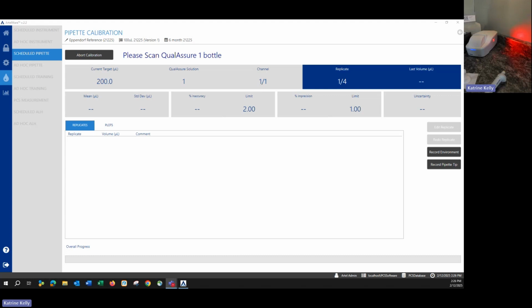And the software is telling me to please scan QualAssure 1 bottle. So there's my range 1 right there. It has a barcode on the side. So I'm going to go ahead and scan that. So this line right here in the software is kind of your command line. It tells you what to do next, lets you know that it's waiting. So now it's saying, please scan reagent Cal A. So here's my Cal A vial. It's a clear vial, has a barcode on the side.